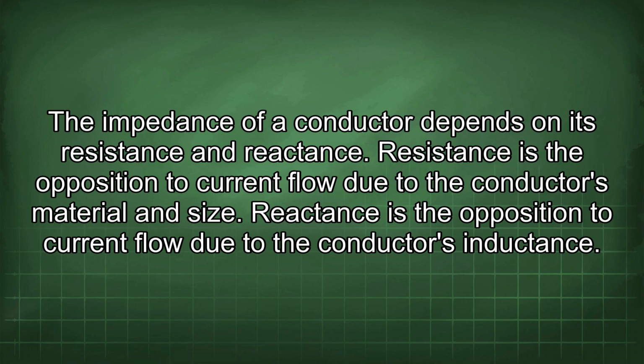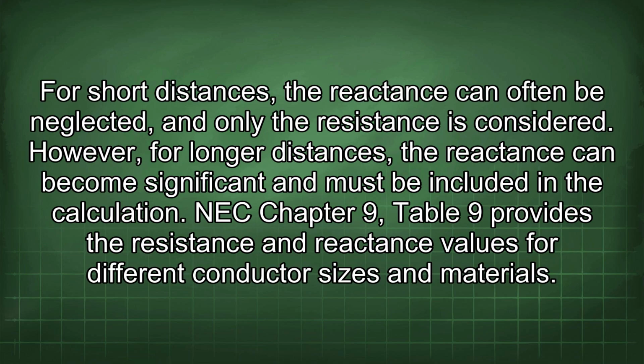The impedance of a conductor depends on its resistance and reactance. Resistance is the opposition to current flow due to the conductor's material and size. Reactance is the opposition to current flow due to the conductor's inductance. For short distances, the reactance can often be neglected and only the resistance is considered. However, for longer distances, the reactance can become significant and must be included in the calculation.